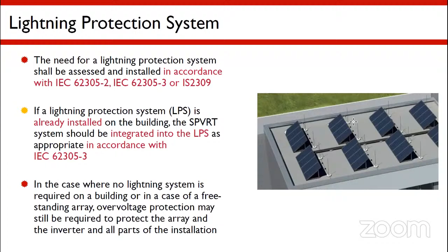If the plant is bigger or utility scale, then obviously the height of the lightning spike should also be more, and the number of lightning arrestors to cover the zone of protection should also be more. So this is also a very important factor. And whatever lightning arrestor you use, you should comply with the standard IEC 62305.